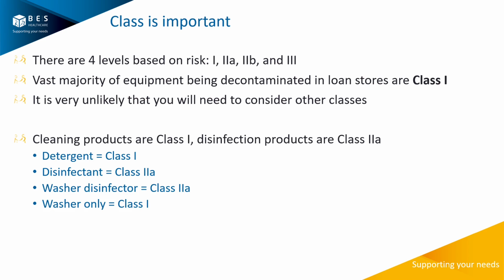Just as an example, when we're looking at decontamination processes, detergents would come under class 1 because they are just cleaning, whereas disinfectants and the actual chemicals would come under class 2A. A washer disinfector would also be 2A because it is doing disinfection, and a pure washer would be a class 1 product.